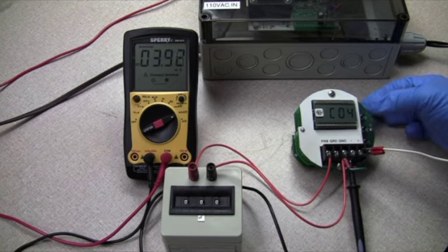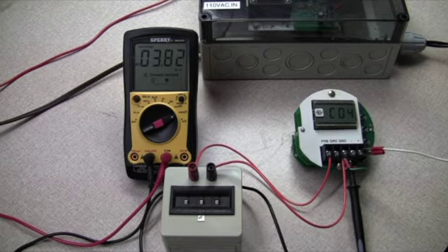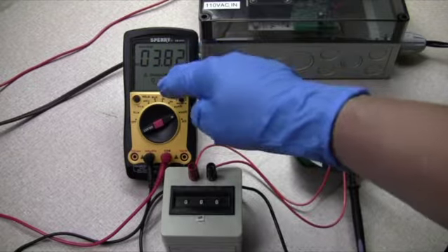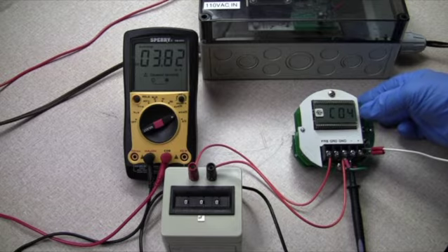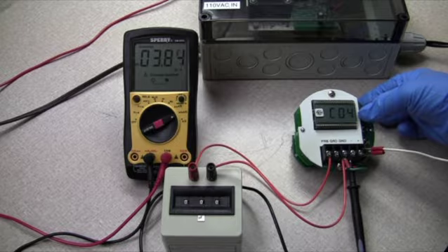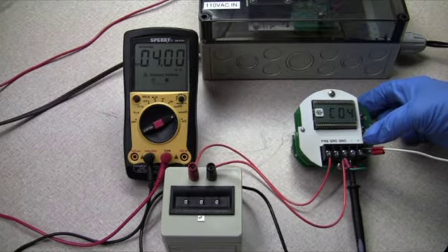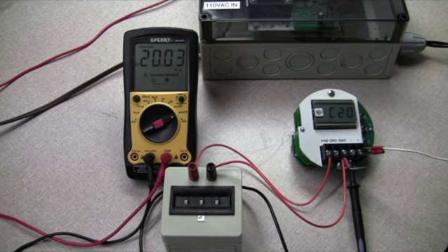This will be done by us at the factory to start out. If this ever needs to be done in the field, you're going to need a meter to do this so you can see where you are in the 4 to 20 milliamp scale. We want to be exactly at 4, or as close to it as we possibly can. So we hit the SW1 button, and that's right on. The SW3 button enters, and we jump up to the 20.